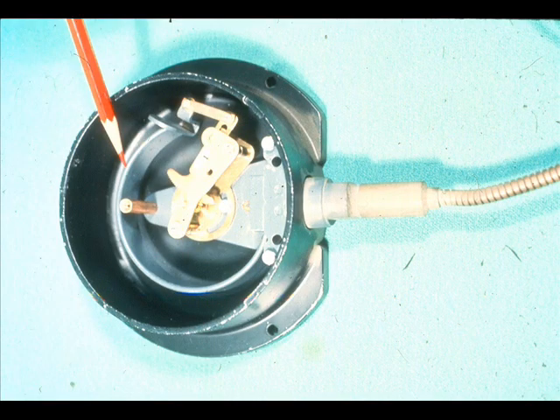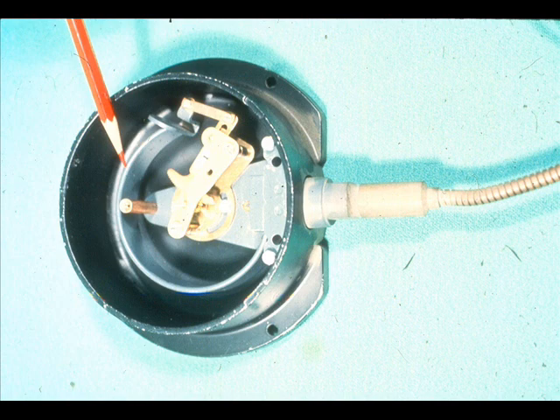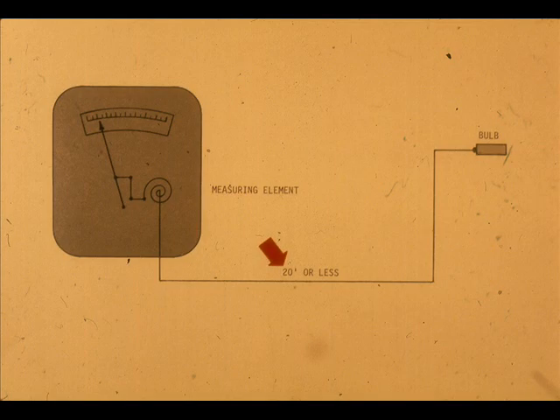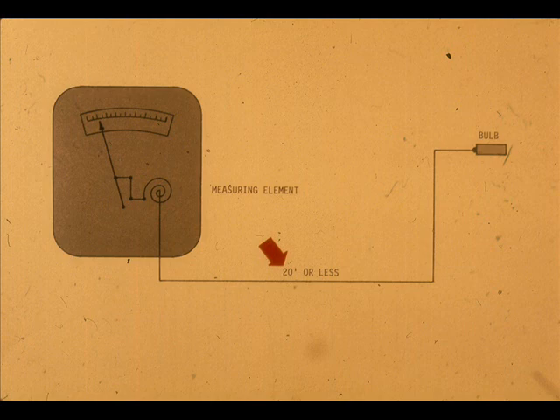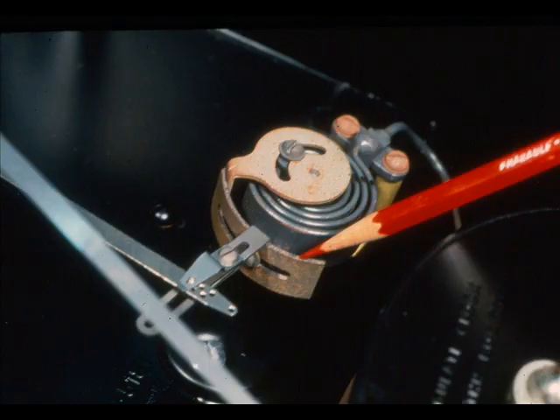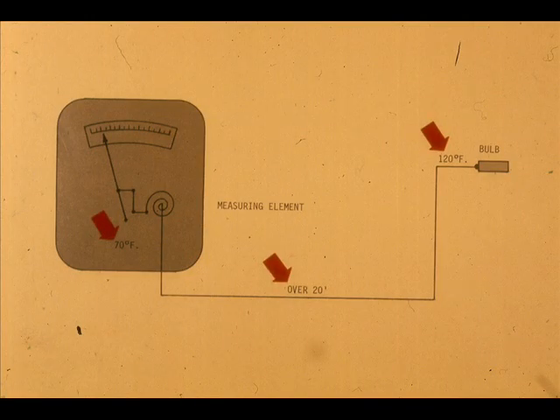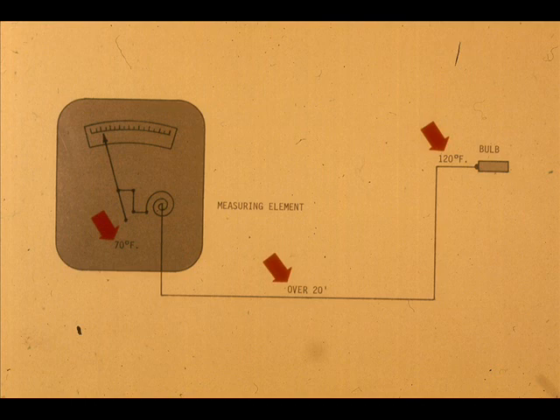An increase in temperature of the capillary or measuring element will cause the readout to change, although not as much as an increase at the bulb because of their lesser volume. Therefore, temperature compensation is required. Usually, if the capillary tubing is 20 feet long or less, only case compensation is required. This is usually done by using a bimetallic strip in the linkage between the measuring element and the pen-driving lever. Some manufacturers use a bimetallic helical element designed to work in opposition to the measuring element for any change in case temperature.